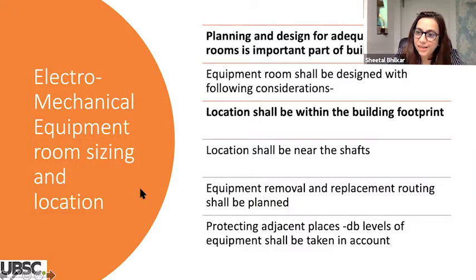While we design the building, service spaces are very important. Electromechanical equipment room sizing and location is very important in any high rise. Planning and designing of adequate equipment spaces is very important, because the equipment room shall be designed so that it is within the building footprint. Its location should be near the shaft. Then equipment removal and replacement routing should be planned in the beginning, because from a maintenance point of view, if you are not planning all these things in the beginning, later on it becomes very difficult.